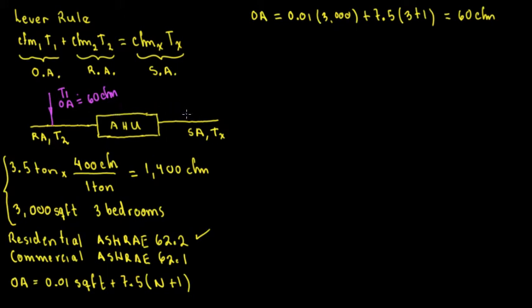The supply air CFM — since it's a 3.5-ton unit — is 1,400 CFM. And since the total is 1,400 CFM, the return air is going to be 1,340 CFM. We now have our CFMs.